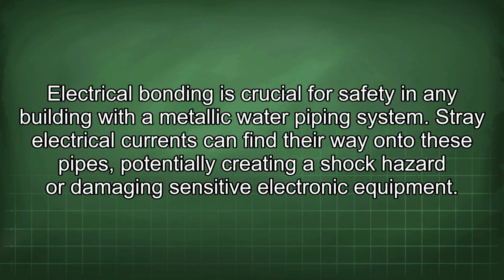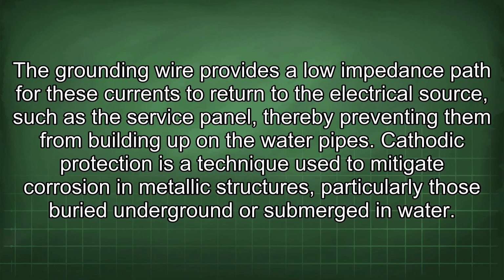Electrical bonding is crucial for safety in any building with a metallic water piping system. Stray electrical currents can find their way onto these pipes, potentially creating a shock hazard or damaging sensitive electronic equipment. The grounding wire provides a low impedance path for these currents to return to the electrical source, such as the service panel, thereby preventing them from building up on the water pipes.